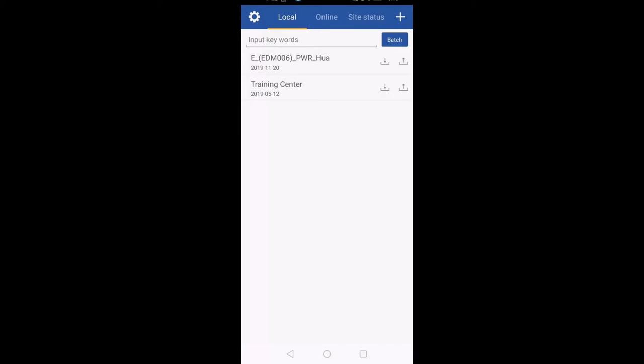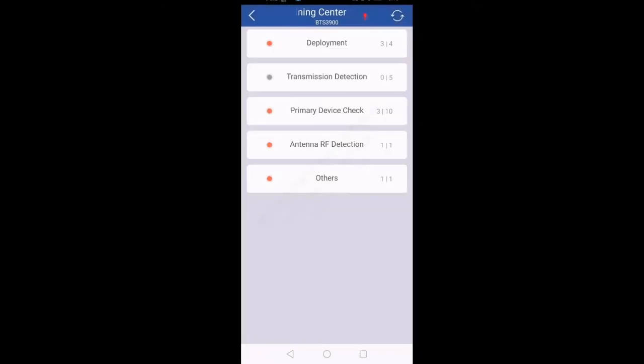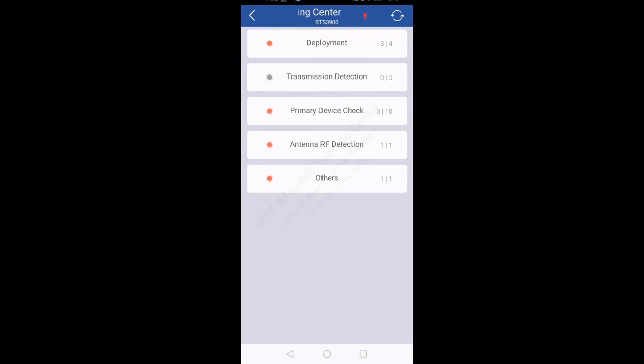Now we downloaded the training center — I will click on Training Center. Once I click on it, I have five options: Deployment, Transmission Detect, Primary Device Check, Antenna RF Detection, and Others. Deployment is for uploading configuration or software to UMPT, or downloading a backup script. Transmission Detection is for ping tests. Primary Device Check is for checking boards. Antenna RF Detection is for checking VSWR values. Others is for checking active alarms.